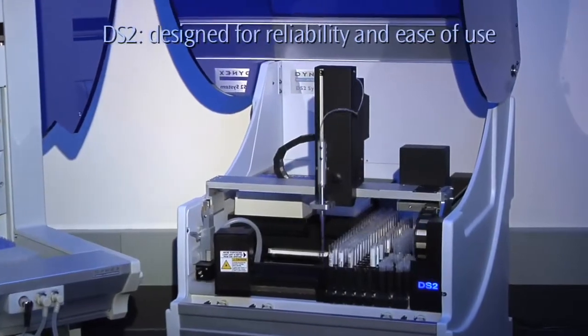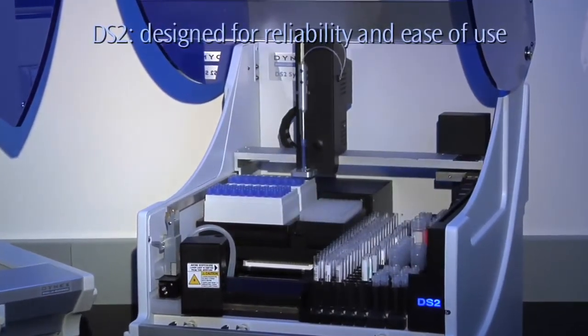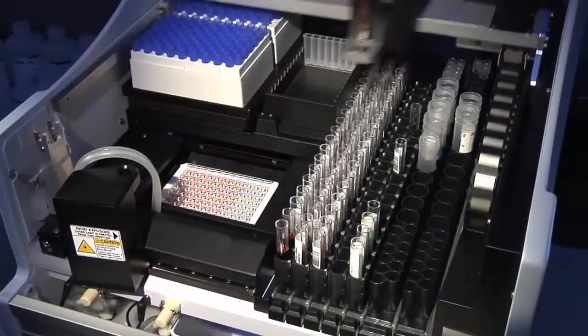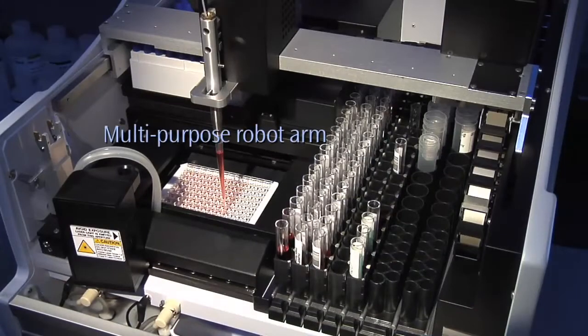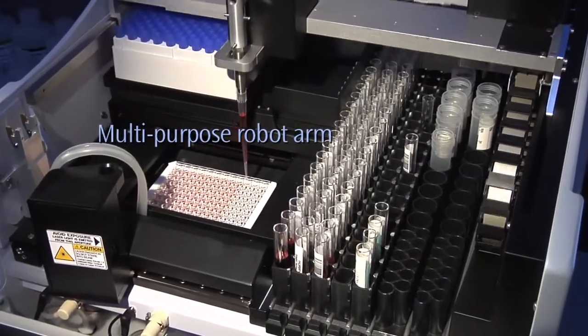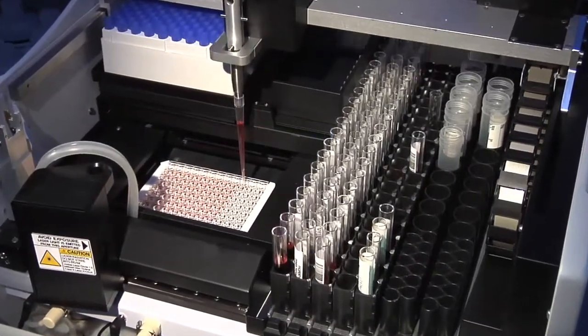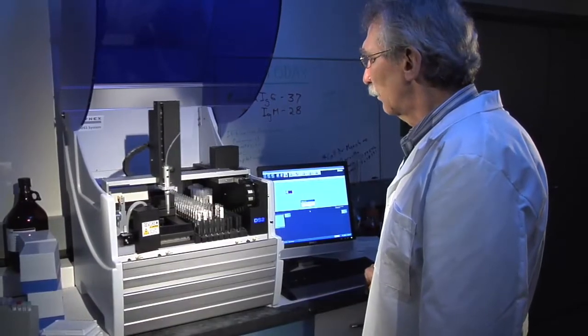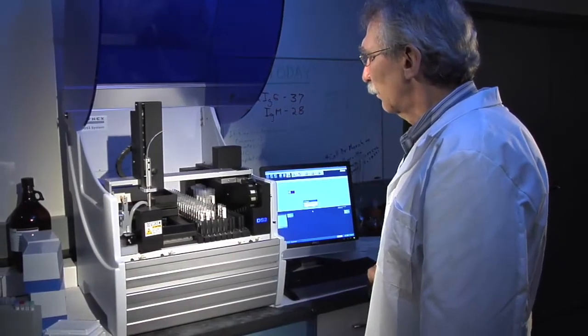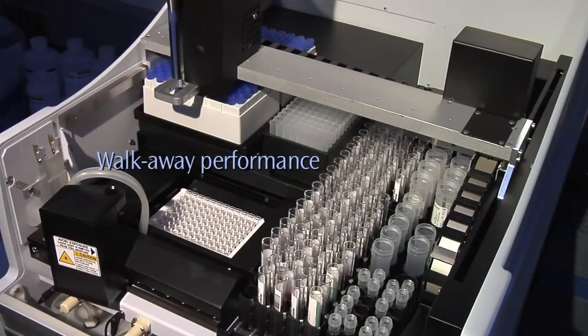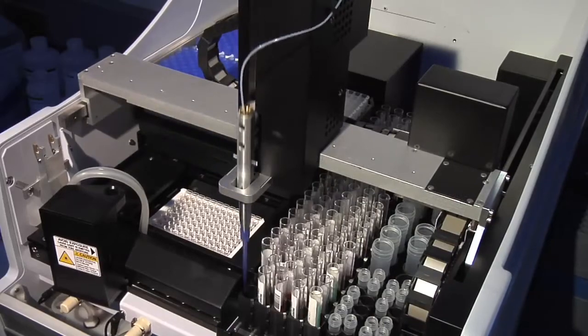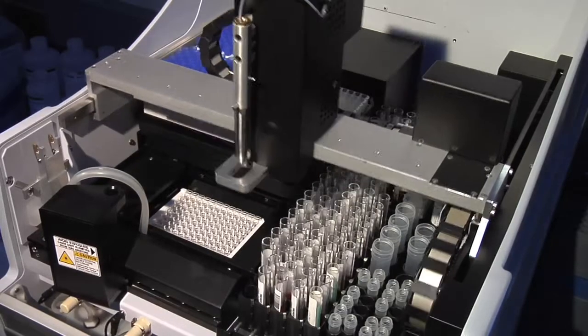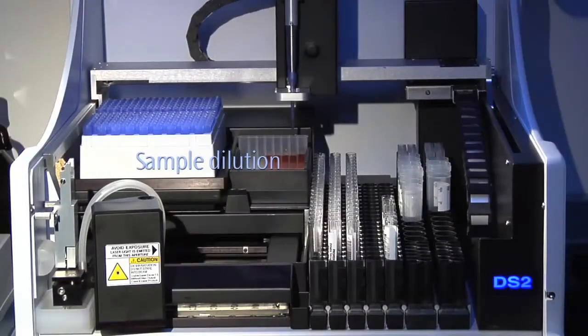Dynex designed the DS2 for reliability and ease of use. It has few moving parts. One multiple-function robot arm does everything from pipetting to operating the optional barcode reader. The DS2 performs all functions automatically that were previously done manually, including sample dilution.